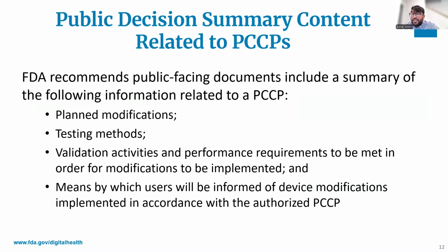In addition, when a device with a PCCP is authorized, FDA recommends that the public-facing decision summary include key information about the PCCP, specifically what proposed modifications are planned, what testing methods will be used, what validation activities and performance requirements must be met before a modification is implemented, and how users will be informed when a modification is made.